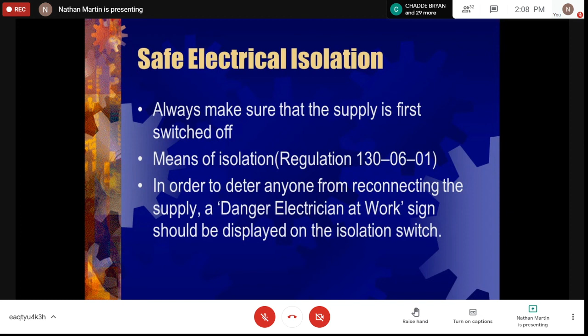Now, safe electrical isolation: always make sure the supply is switched off, which is your means of isolation, regulated by IEE 130-06-01. That regulation requires every electrical circuit to have a means of isolation. In order to deter anyone from reconnecting the supply, a danger electrician at work sign should be displayed on all isolations.